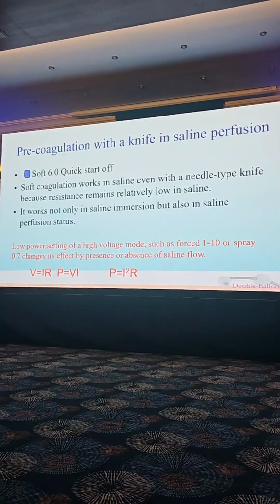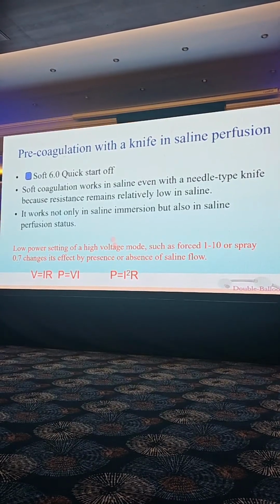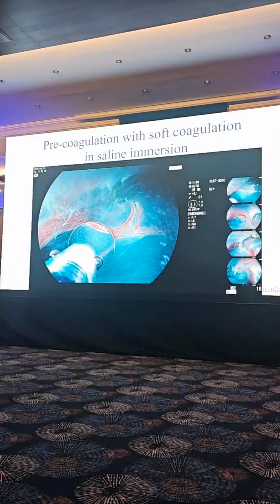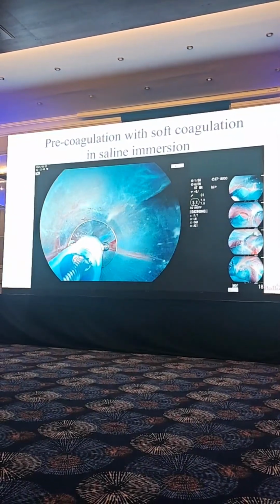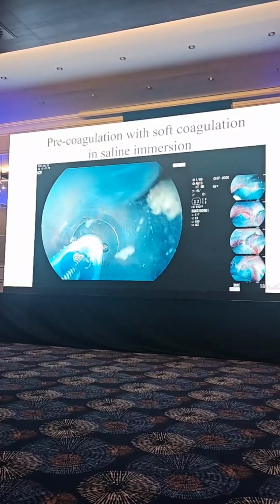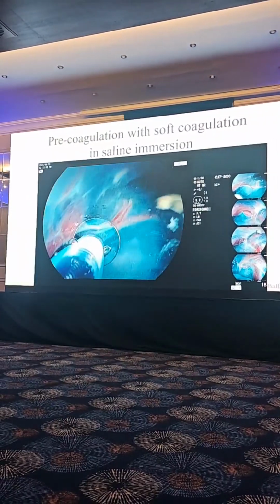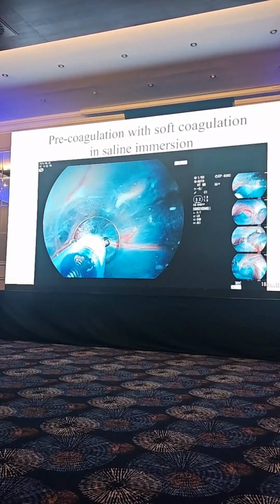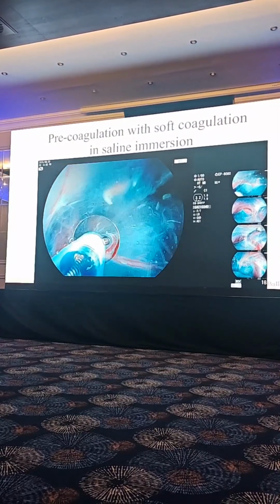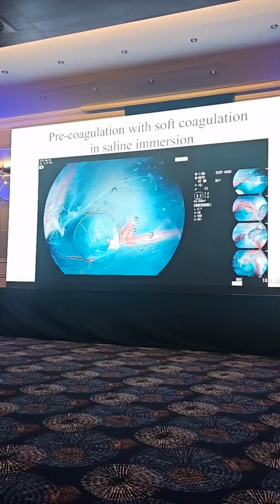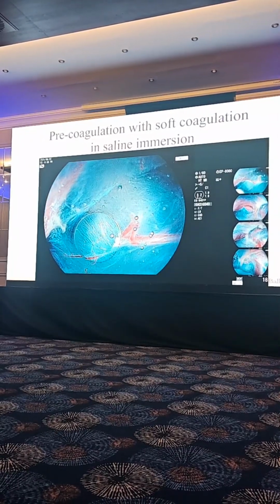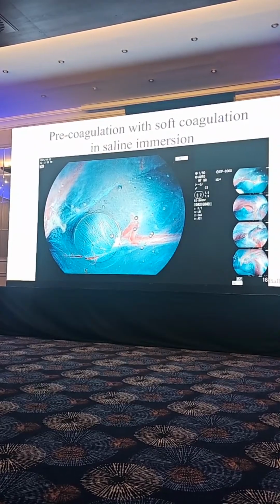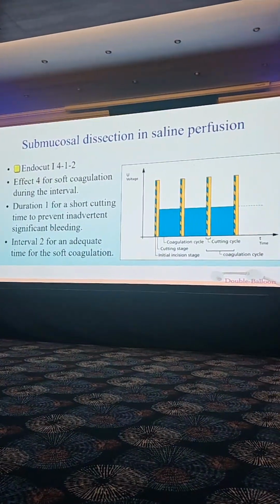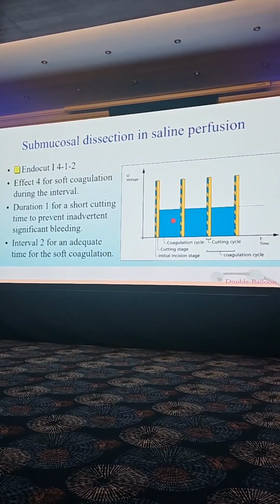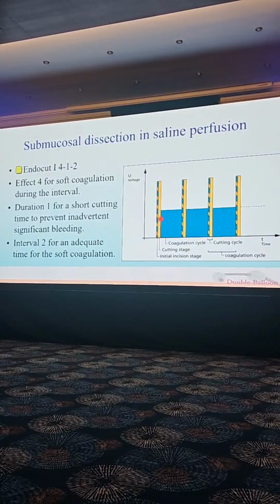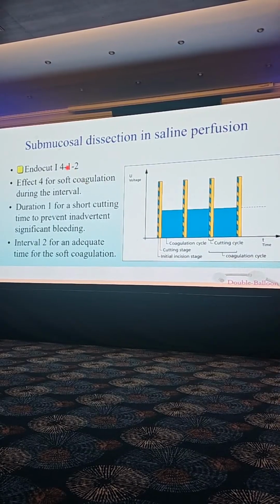So if the resistance doesn't go up in the saline, I thought soft coagulation should work in the saline. The soft coagulation didn't work in CO2 because resistance goes up and current stops. But in the saline, even with 200 volts, the current still goes on. So it should work, I thought, and it worked. So that's the reason why, if the soft coagulation works, then the soft coagulation between the cutting current, that is the Endocut mode effect, should work.